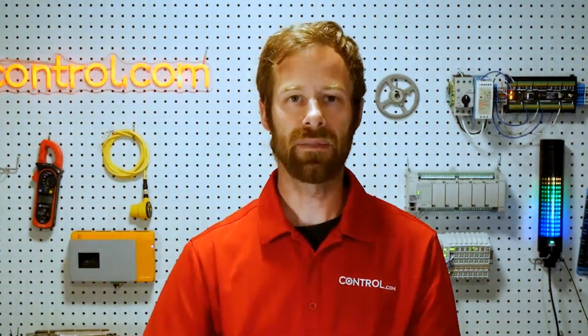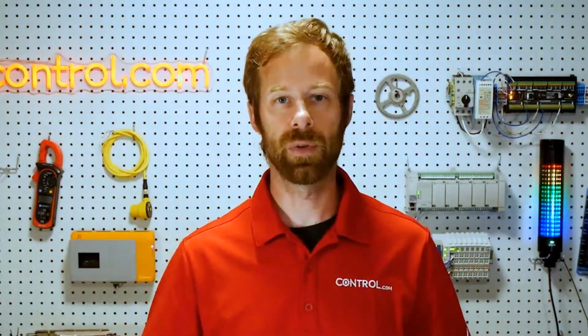But we do also have to be very careful about voltage versus current when we're selecting analog inputs. Some modules can be selected either way, but a lot of modules cannot. So if we have an AI module, the AI part number may have a 1 or a 2 or a version A and B or slight revisions in that part number that tell us the difference between voltage and current, and we need to make sure to choose the right one based on the sensor that we've got.